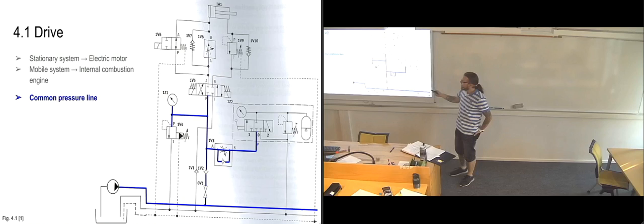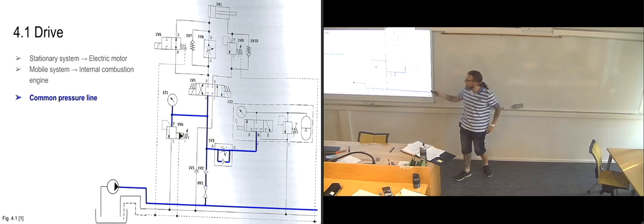So this one will have a sort of pilot pressure here. So a very thin connection to the pressure line, which allows just a little bit of the fluid to move in here and push on this one. And once it pushes hard enough to counteract this spring over here, then the arrow will be moved over so that it's directly in line with the rest, so that then it will move directly back to the tank. We will be looking a bit more in detail on that one a bit later.